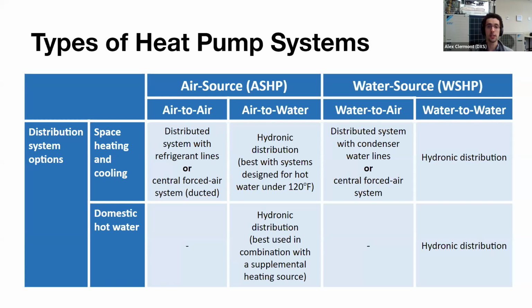Now, water source heat pump is usually known as water to air, which is where you have a condenser water loop in a building and you have a bunch of water source heat pumps that heat or cool the space. But there's also water to water systems, which we'll talk about in a little bit, and those are also starting to be used for domestic hot water. Again, this sounds very confusing, all these different options, but this is to explain that the word heat pump can actually mean a lot. Is it an air source or a water source heat pump? Is it heating and cooling air? Is it heating and cooling water? Once you have that information, you can start figuring out what kind of machine you're looking at.